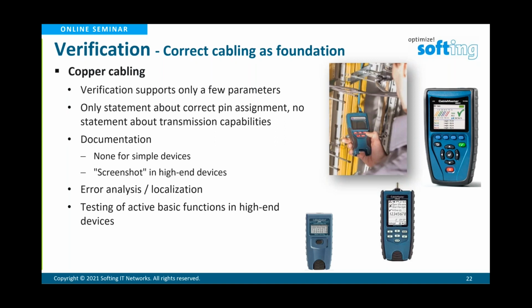Error analysis and localization is possible if you have a TDR built in, so that you can also find shorts in the cabling runs. Opens are usually capable of being found even if you don't have a TDR built in, but for shorts you need a TDR. Testing of active functions in the high-end units is something that we see more often today. So the Cable Master 600, 800 have some really nice things built in, like you can ping, you can trace route, you can test for DHCP and all this other stuff. So this is a fairly good small instrument if you are supporting small networks.